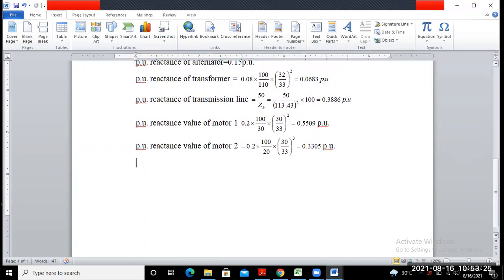So when we solve for the transmission line, that means the reactance given to you in this one, for the transmission line we already solved that one. X base equals kilovolt base whole square by MVA base new. So the total length of the transmission line is given to you, 200 kilometers. Okay, so just multiply by 200.